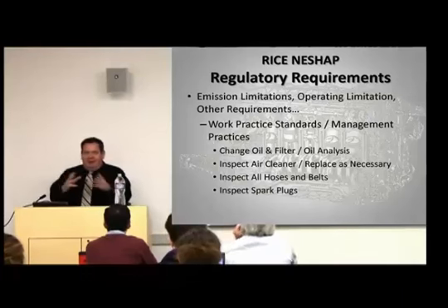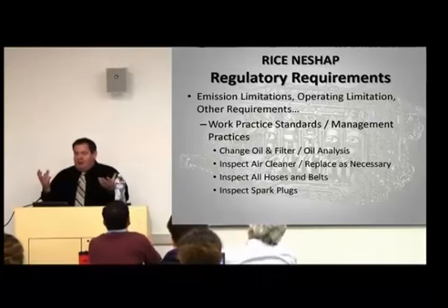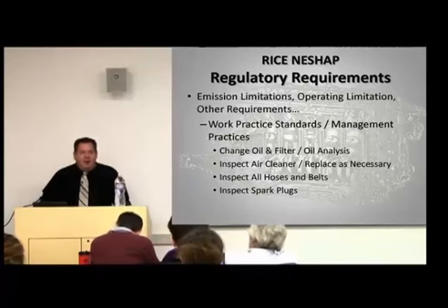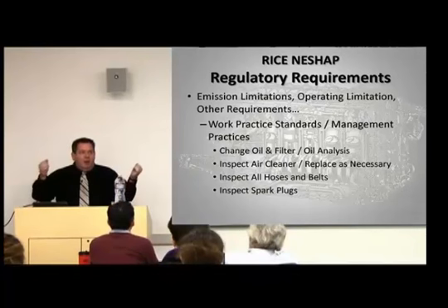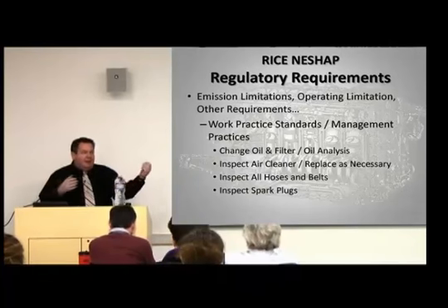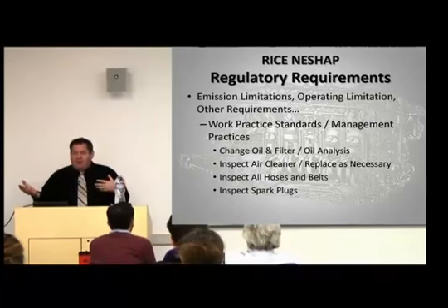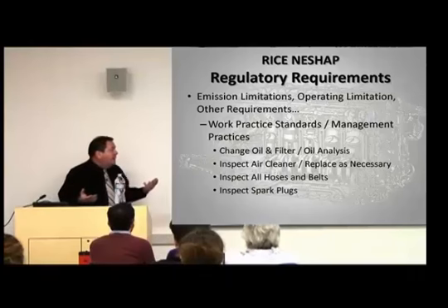So sometimes you have little air filters that are just like your car air filters, a little paper element; hold it up to the light and see if you can see through it. And sometimes your air filter assemblies are pretty complex items. But either way, if you're asking about this, you want to look at both sides of an air filter if you can, because they might just show you the clean side. One side will always be clean, no matter how dirty the air filter is. Or you can look at paperwork to see if they're inspecting it.